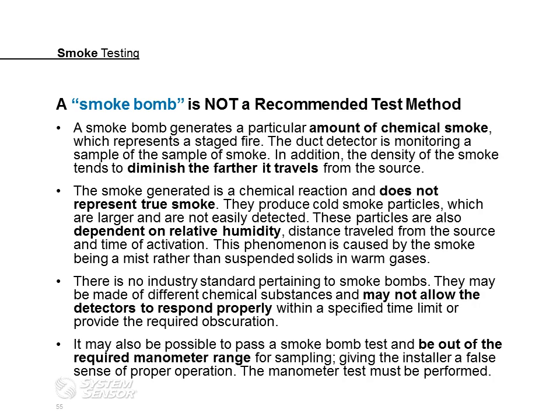The next slide that I want to talk about is pretty important. I run into it a lot in the field when we talk about testing: the use of smoke bombs. If you look at what UL and NFPA both state as far as recommended testing, they both reference the manufacturer's recommended, acceptable testing. Smoke bombs are not a recommended test method.